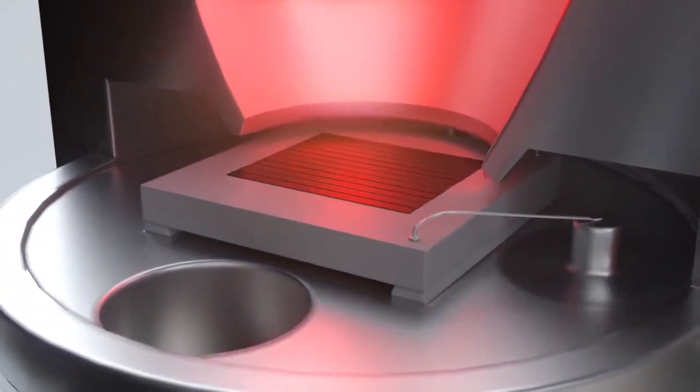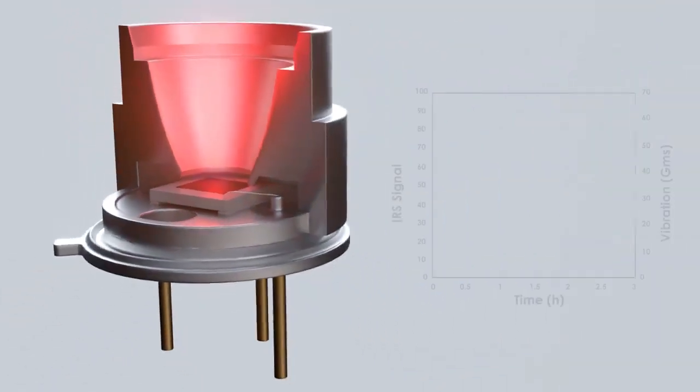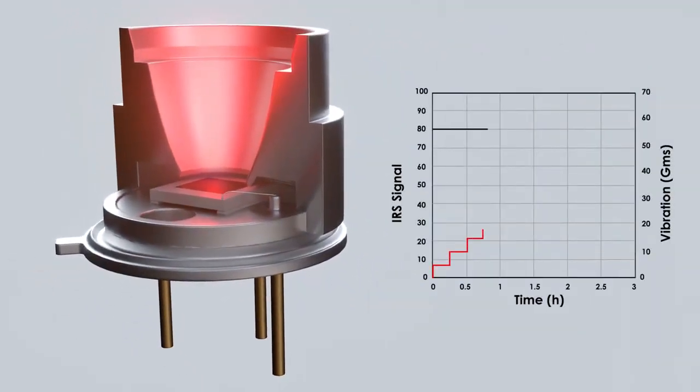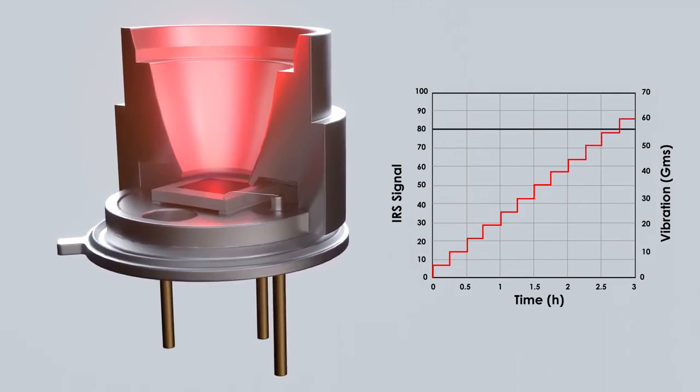Furthermore, the chip is attached to the TO header with an elastomeric adhesive, and can thus efficiently absorb vibrations. This entire design makes the Exatris infrared source extremely resistant to external disturbances.